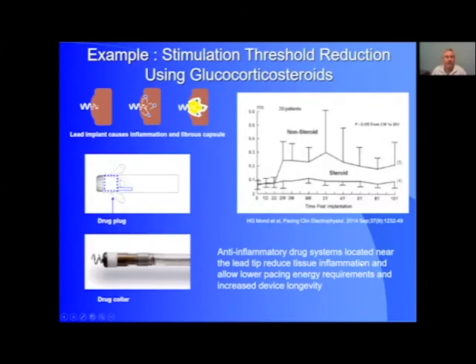Okay, so a few examples then. So the first application that we got into, and has been around for many years, is a drug-eluting cardiac pacing lead. So it was found many years ago that incorporation of steroids into the region where a cardiac pacing lead is implanted in the heart muscle wall can have benefits in terms of minimizing the fibrous capsule buildup around the implant. So basically, in this upper left illustration, you can have a helical coil that provides the pacing implanted into the muscle wall, and when that's implanted, there's a fibrous reaction that can form a capsule around that implant and can raise the resistance of the lead to provide effective stimulation.